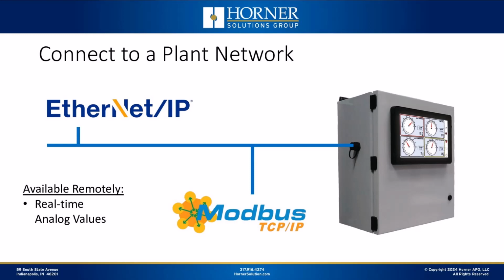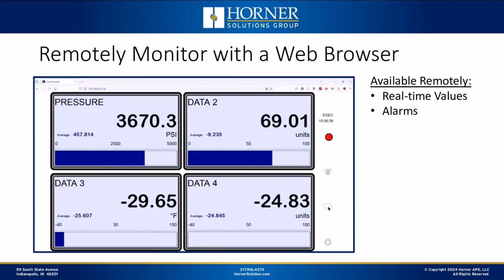And then it also supports Modbus TCP IP as a server, which means, again, if you want to get those process variable values into a SCADA package or a different PLC or somewhere else using Modbus protocol, Modbus TCP protocol, you can do that without any difficulty. So it's got connectivity built right into it.